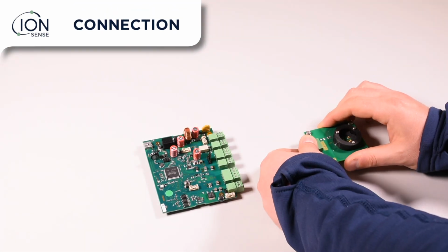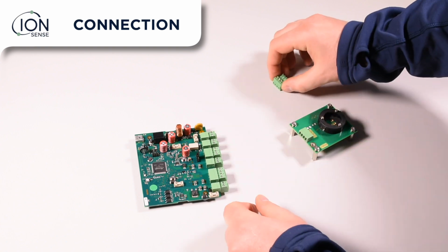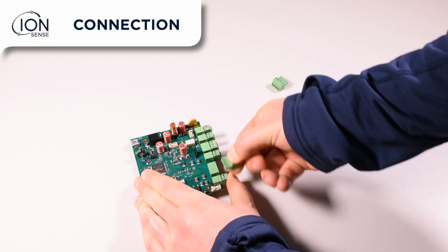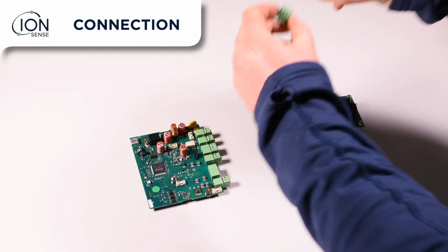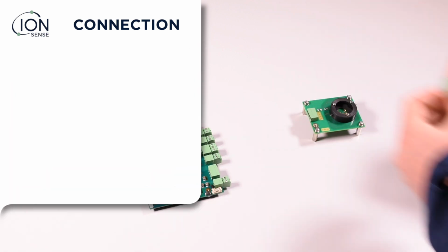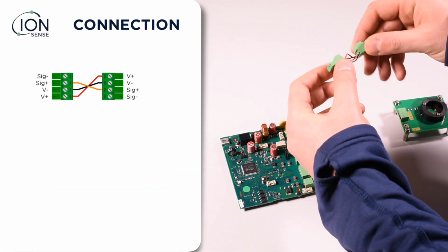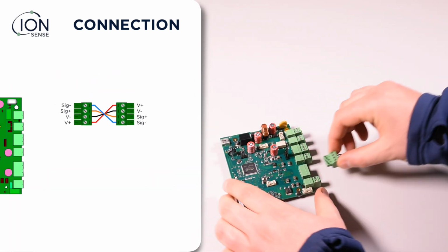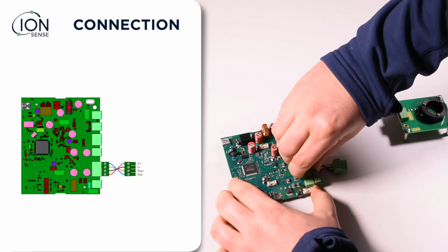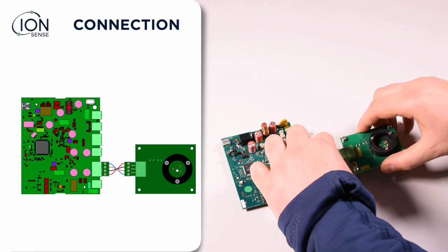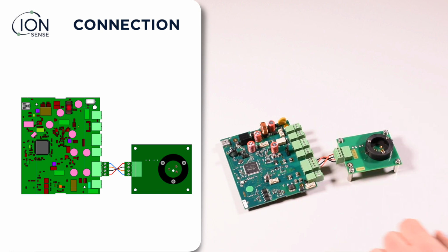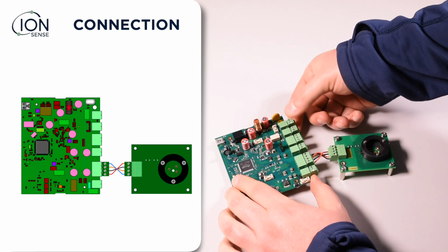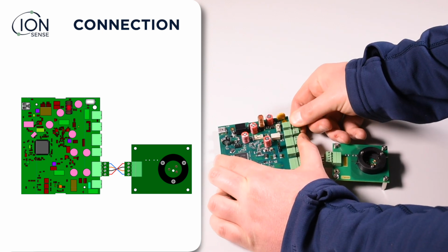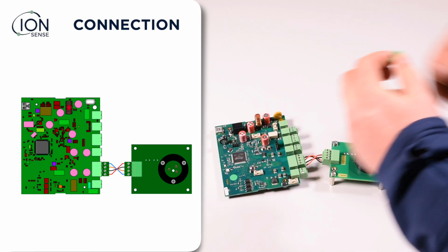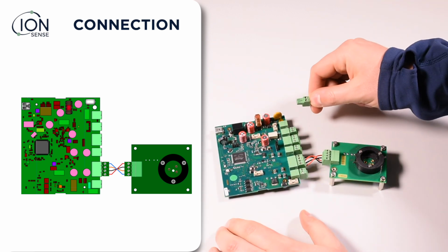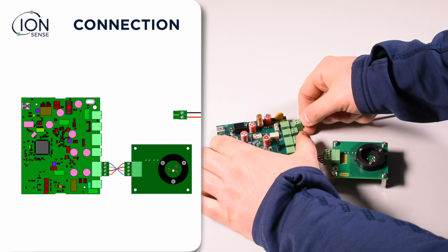To connect the sensor board to the control board, remove the four-way connectors. Now wire these connectors, following this diagram. If the sensor board is mounted more than 100 mm from the control board, screened cable should be used. Now remove the power connector from the control board and connect a DC power supply. But don't switch the power on.